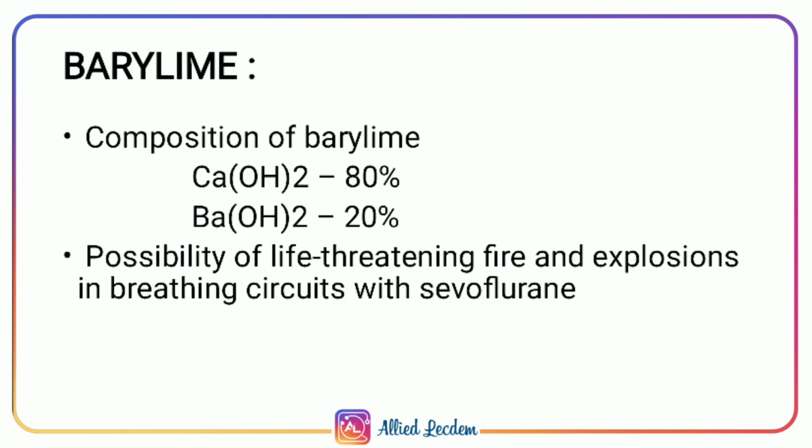Baralyme, another type of CO2 absorbent, which has 80% calcium hydroxide and 20% barium hydroxide, has been withdrawn from the market because of the possibility of life-threatening fire and explosion in the breathing circuit with sevoflurane, which is an inhalational anesthetic agent. The similar thing between soda lime and baralyme is that they can produce compound A on reaction with sevoflurane, which is nephrotoxic to humans.